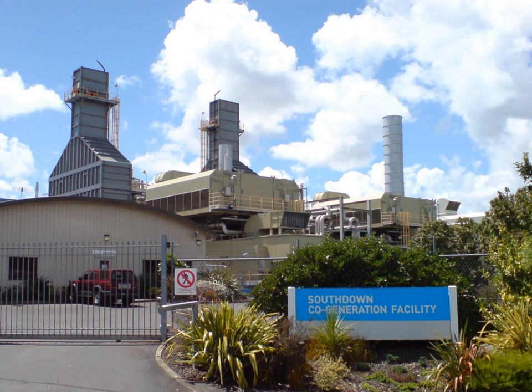In a traditional power plant delivering electricity to consumers, about 34.4% of the heat content of the primary heat energy source — such as biomass, coal, solar thermal, natural gas, petroleum or uranium — reaches the consumer, although the efficiency can be 20% for very old plants and 45% for newer gas plants. In contrast, a CHP system converts 15% to 42% of the primary heat to electricity, and most of the remaining heat is captured for hot water or space heating. In total, over 90% of the heat from the primary energy source can be used when heat production does not exceed the thermal demand.